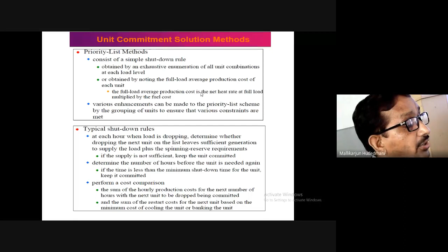Let's see the theory behind it. Explain the priority list method using a flow chart. This was a question you got in the earlier academics itself. Let's see how it starts. Initialize your setup and start the algorithm. Then calculate the minimum number of units that must be run to carry the load plus spinning reserve every hour. This is your first task once you decide your system.